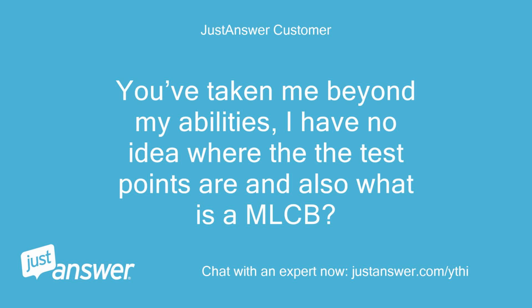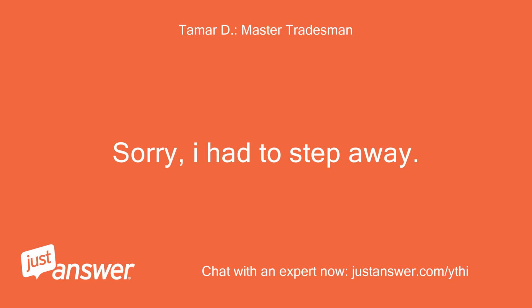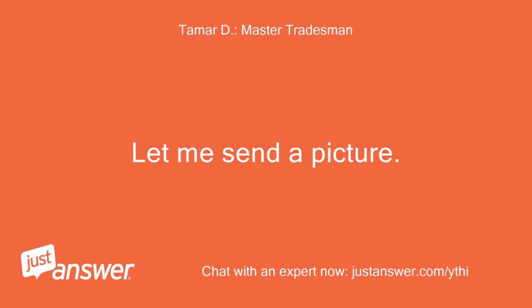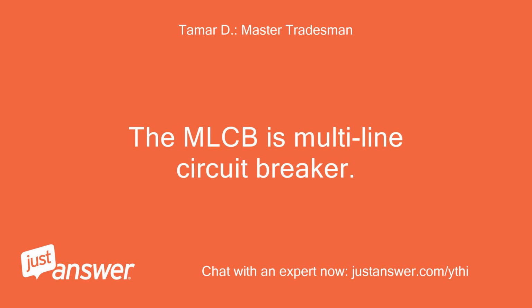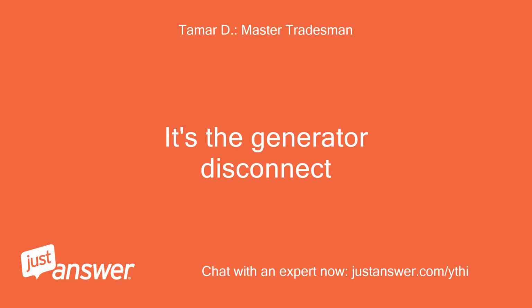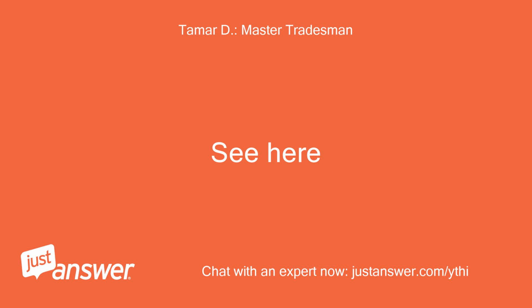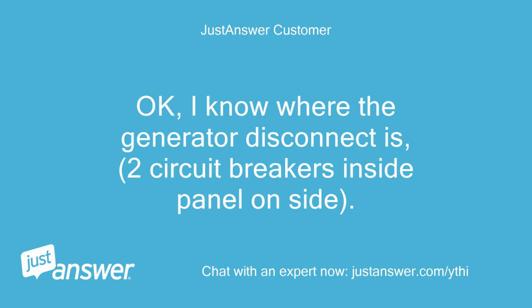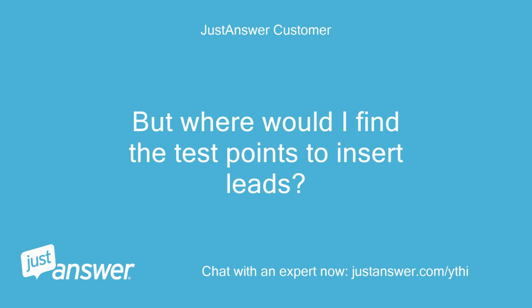You've taken me beyond my abilities. I have no idea where the test points are, and also what is an MLCB? Sorry, I had to step away. Let me send a picture. The MLCB is the multi-line circuit breaker. It's the generator disconnect. See here. Okay, I know where the generator disconnect is, two circuit breakers on the side panel. But where would I find the test points to insert leads?